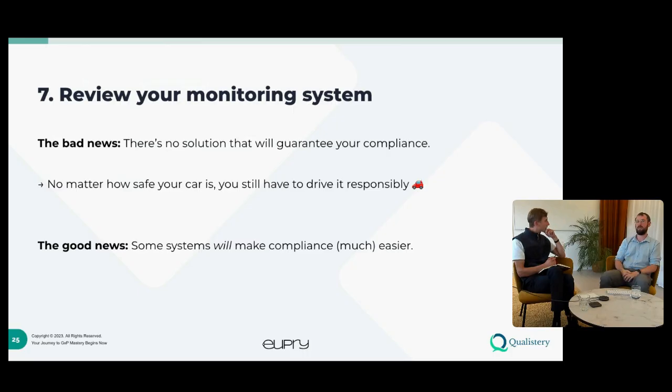One of the requirements, as an example from Part 11, is that you need to be able to authenticate persons using the system. So how do you know that a person is actually that person? Do you need to see a driver's license? Do you need social security or identification or so forth to make sure that person is actually that person? And through that, you still have to review it, and you still have to do that manually. Some systems can do that, often very complicated systems, but yet again, there are other areas in which you need your process in place rather than relying on the system.